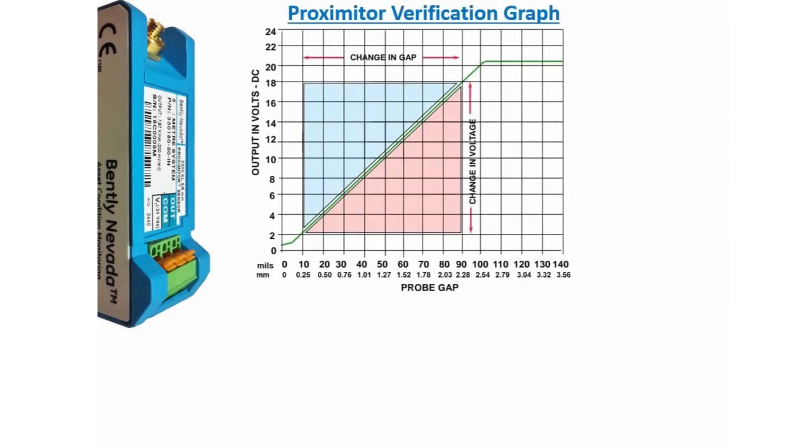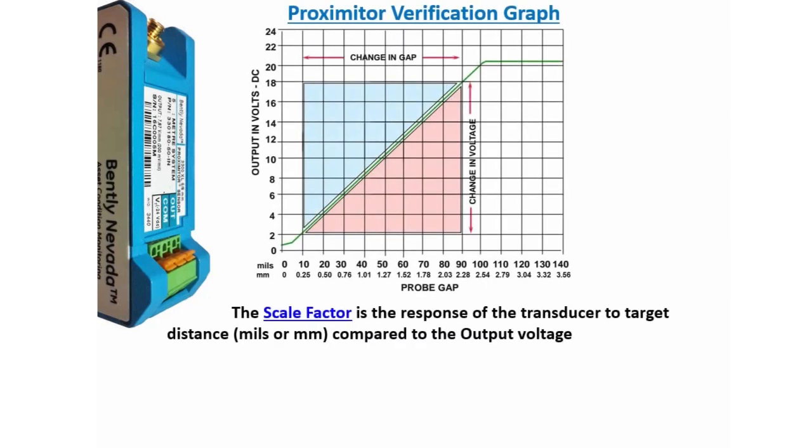Before moving on to the next step of verification, we should know the definition of scale factor. The scale factor is the response of the transducer to target distance in mils or millimeters compared to the output voltage. So, the scale factor of a transducer is defined as the change in output per change in input.